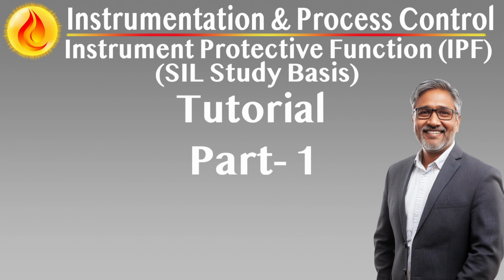Functional independence and avoidance of common cause failures. IPFs must operate independently of basic control and alarm systems to ensure integrity under failure or upset conditions. Independence extends to hardware separation, power supply, signal conditioning, logic solvers, and final elements. Shared components or pathways are only permitted if a detailed common cause failure analysis demonstrates acceptable risk.